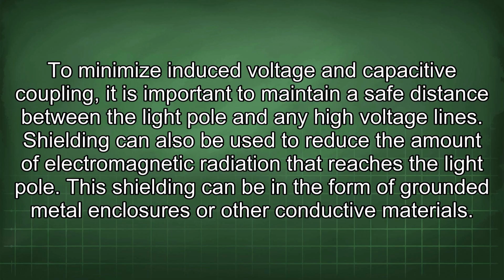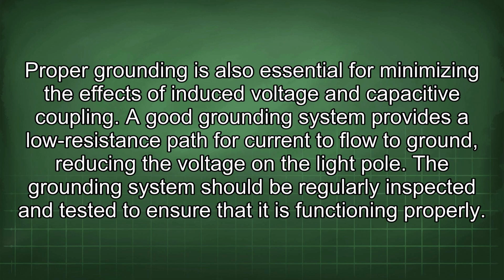Shielding can also be used to reduce the amount of electromagnetic radiation that reaches the light pole. This shielding can be in the form of grounded metal enclosures or other conductive materials. Proper grounding is also essential for minimizing the effects of induced voltage and capacitive coupling. A good grounding system provides a low resistance path for current to flow to ground, reducing the voltage in the light pole. The grounding system should be regularly inspected and tested to ensure that it is functioning properly.